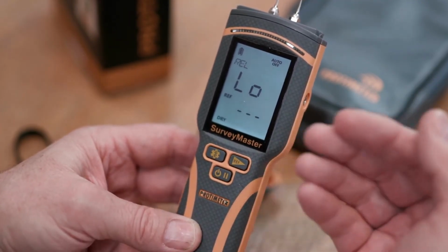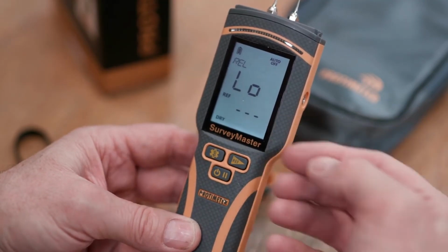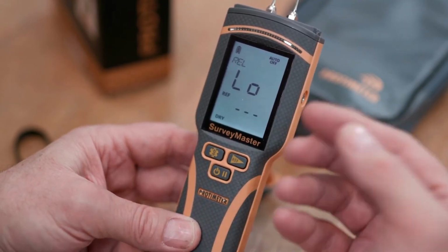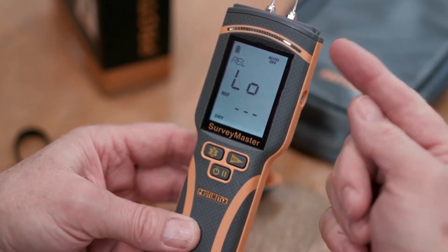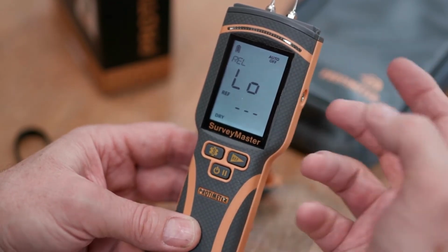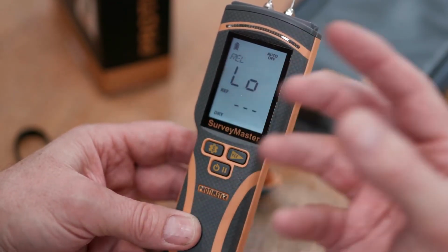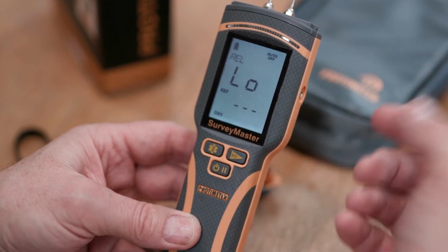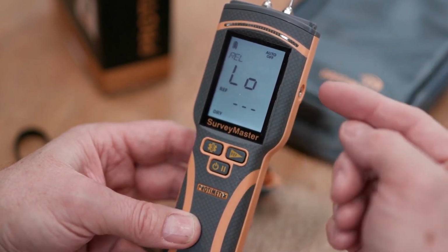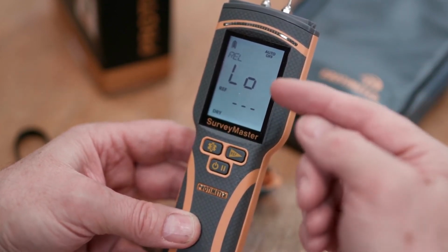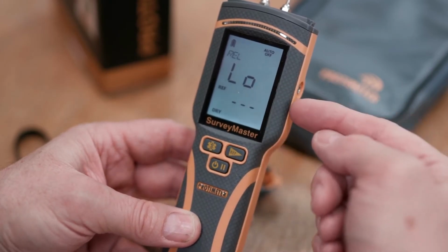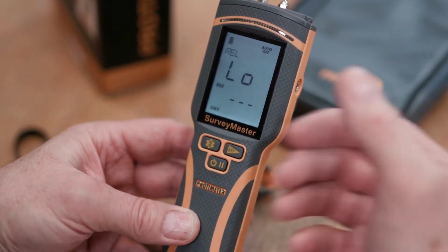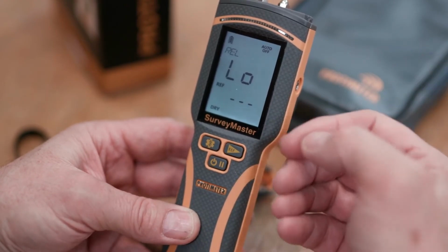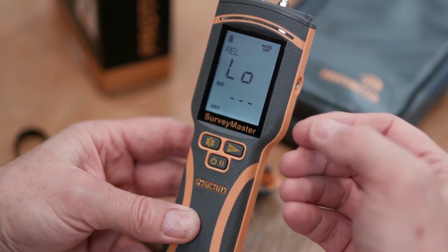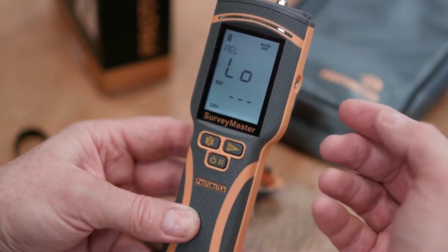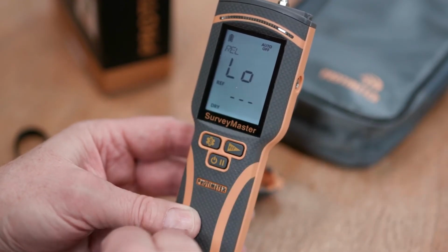The other function is that the meter has the ability to self-calibrate and check calibration. So for the pins, every 50 times the meter turns on or off, it'll check the calibration of the meter automatically and tell you right on the screen whether it's passed. It'll also give you the ability to recalibrate the non-invasive function of the meter. So you do that by holding it in air and going through that. This gives you the confidence that the meter is in calibration all the time. So as I said, it does it every 50 times, but you can also initiate that with button presses.